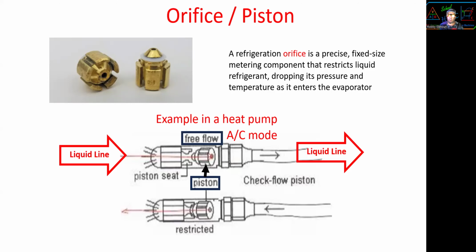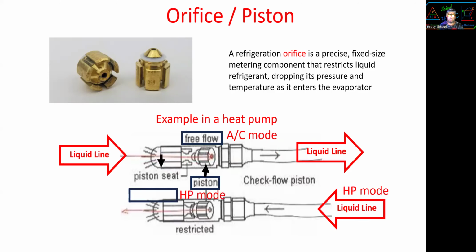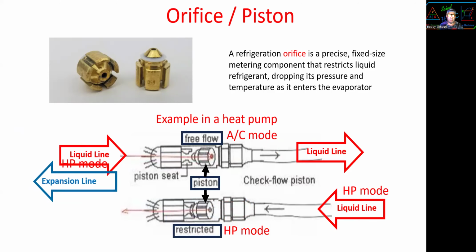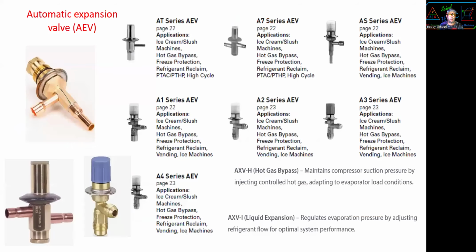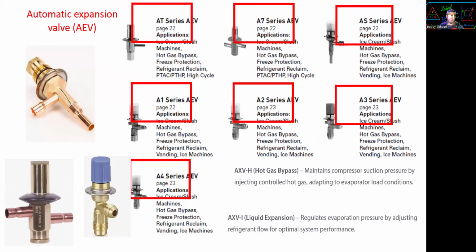All right, it's just regular liquid line. But in heat pump mode, it becomes the metering device, expansion. Alrighty, let's move now to the automatic. No more cap tube and piston, and not much now. Automatic expansion valves. Many applications for the automatic, but mostly for small stuff.